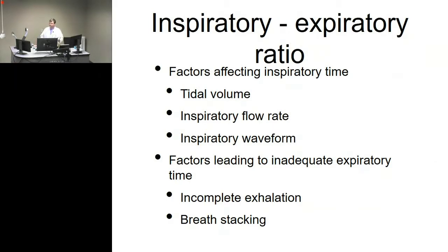Now the Maquet ventilators, which I think we're phasing out, but we still have a lot of them here, don't necessarily have a specific flow on it, but flow is set by your inspiratory to expiratory times, and that is set, and you'll see that on the Maquets.